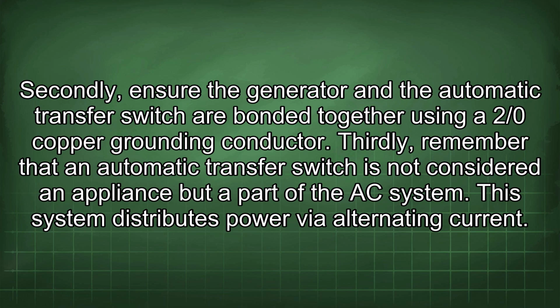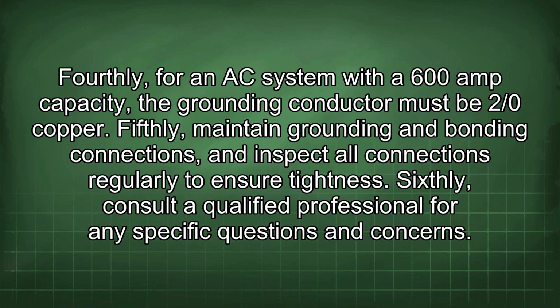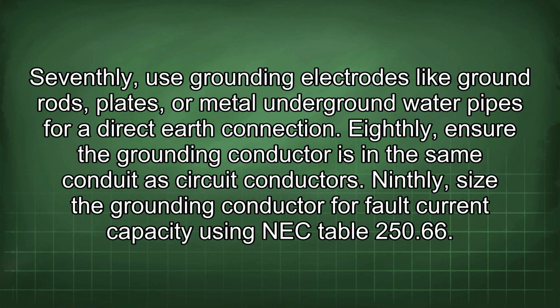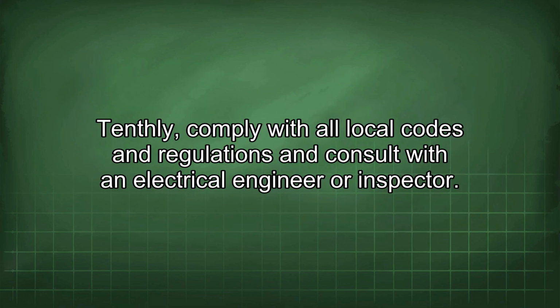Thirdly, remember that an automatic transfer switch is not considered an appliance but a part of the AC system. This system distributes power via alternating current. Fourthly, for an AC system with a 600 amp capacity, the grounding conductor must be 2/0 copper. Fifthly, maintain grounding and bonding connections and inspect all connections regularly to ensure tightness. Sixthly, consult a qualified professional for any specific questions and concerns. Seventhly, use grounding electrodes like ground rods, plates, or metal underground water pipes for a direct earth connection. Eighthly, ensure the grounding conductor is in the same conduit as circuit conductors. Ninthly, size the grounding conductor for fault current capacity using NEC Table 250.66. Tenthly, comply with all local codes and regulations and consult with an electrical engineer or inspector.